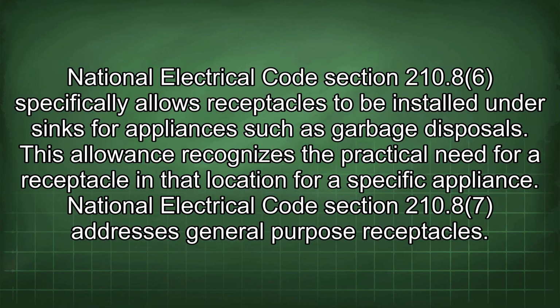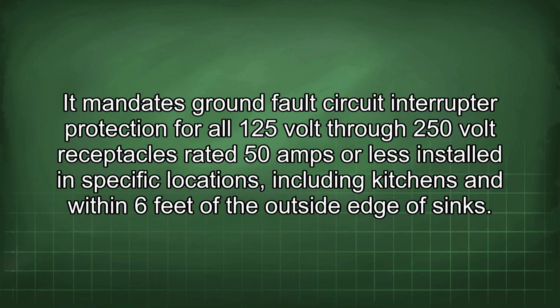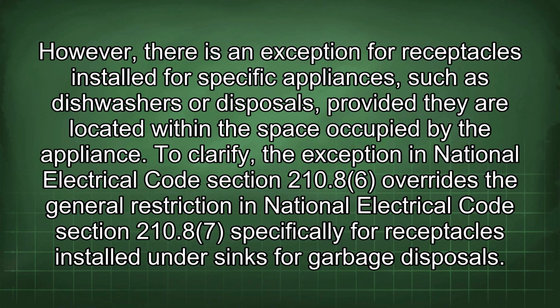National Electrical Code Section 210.87 addresses general-purpose receptacles. It mandates ground fault circuit interrupter protection for all 125V through 250V receptacles rated 50 amps or less installed in specific locations, including kitchens and within 6 feet of the outside edge of sinks. However, there is an exception for receptacles installed for specific appliances, such as dishwashers or disposals, provided they are located within the space occupied by the appliance.